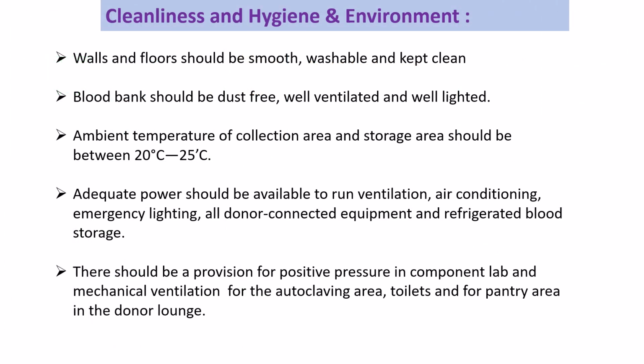The facility should meet the following environmental and infrastructure standards. The walls and floors should be smooth, washable and kept clean at all times. The blood bank must be dust free, well ventilated and well lighted, and the ambient temperature in both the collection and storage areas should be maintained between 20 to 25 degrees Celsius. There must be adequate power to support ventilation, air conditioning, emergency lighting, all donor connected equipment and refrigerated blood storage. There should also be positive pressure in the component laboratory, and mechanical ventilation should be provided for the autoclaving area, the toilets, and the pantry area in the donor lounge.